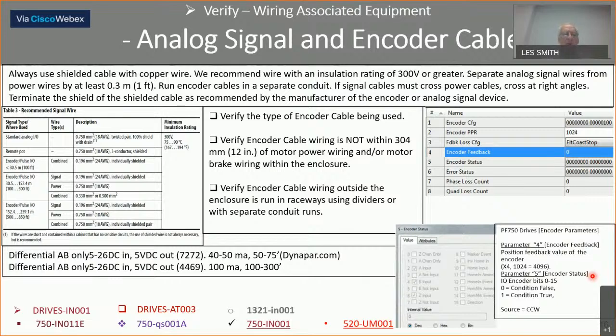Another thing that I brought out here, analog signals. And this happens to deal with an encoder. If we take a look over here, the important thing to see here is that a 24 gauge wire can run 300 to 400 feet off an encoder and be accurate. However, the power cable, the power to that encoder may have to go up to an 18 gauge, but this shows you the various cables that should be there. One thing about encoder cables, look at the vendor spec. We need low capacitance cables.